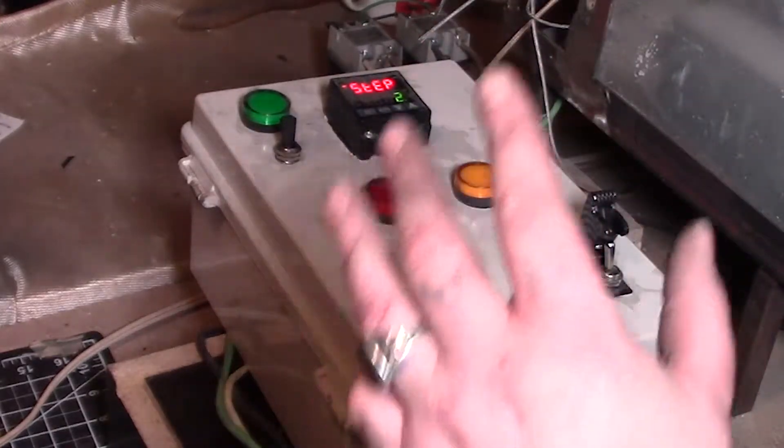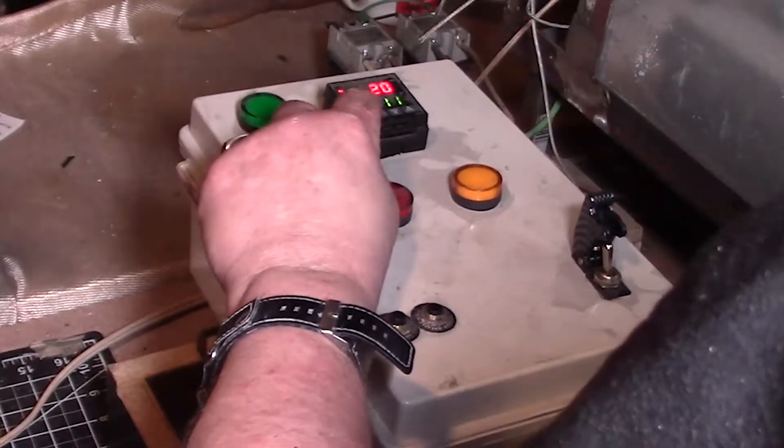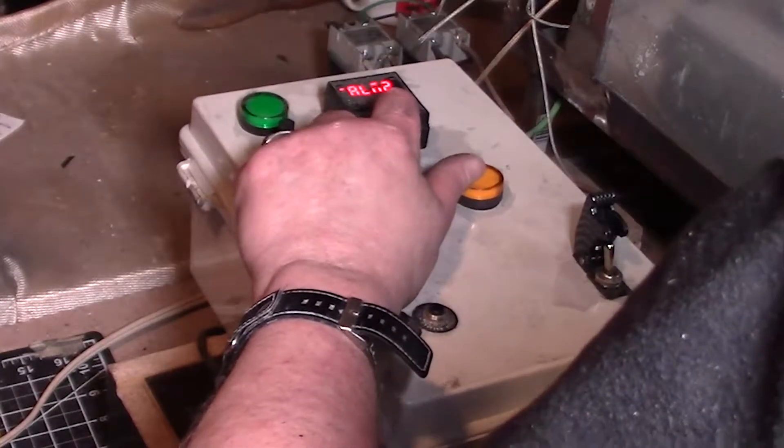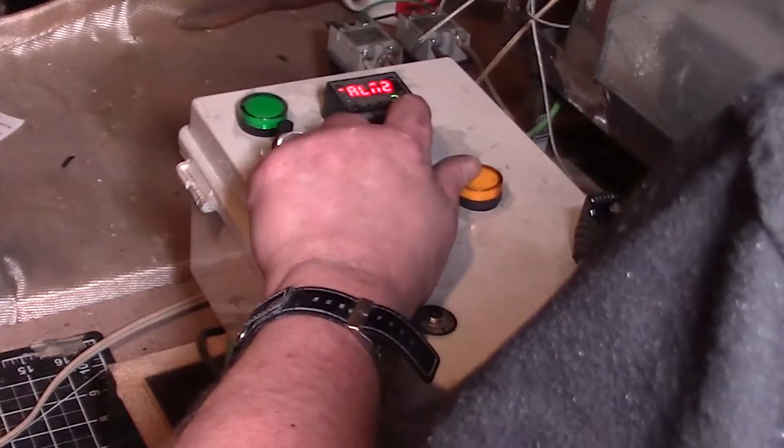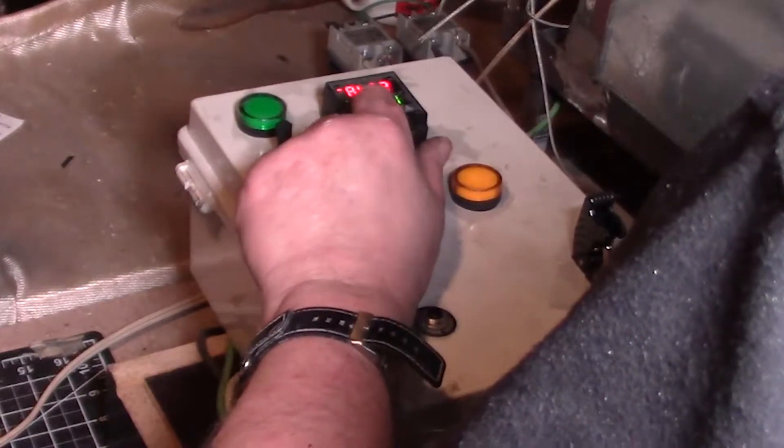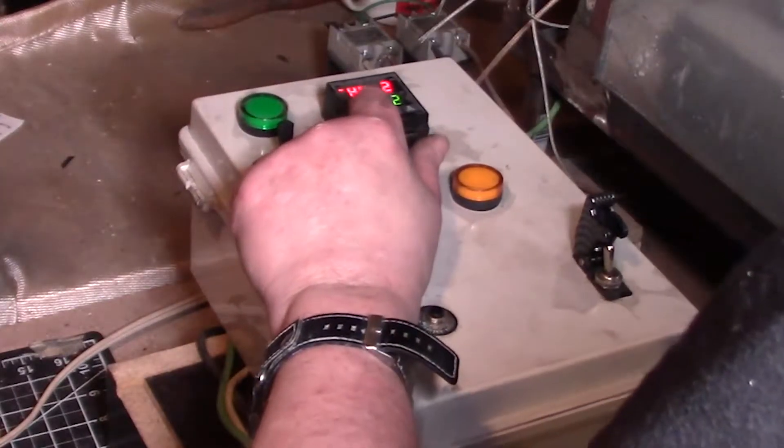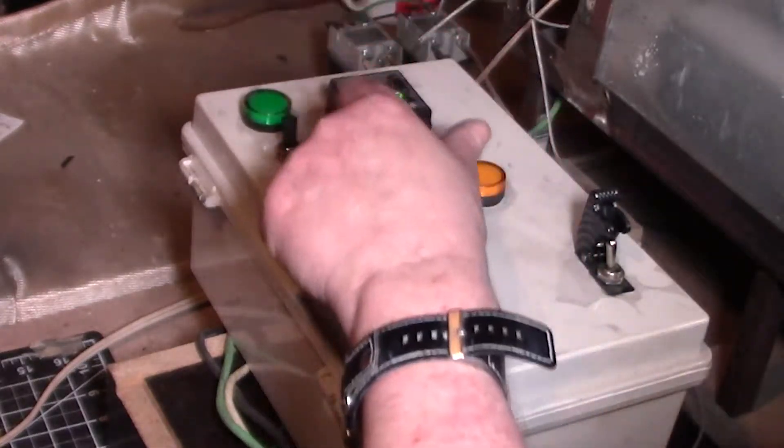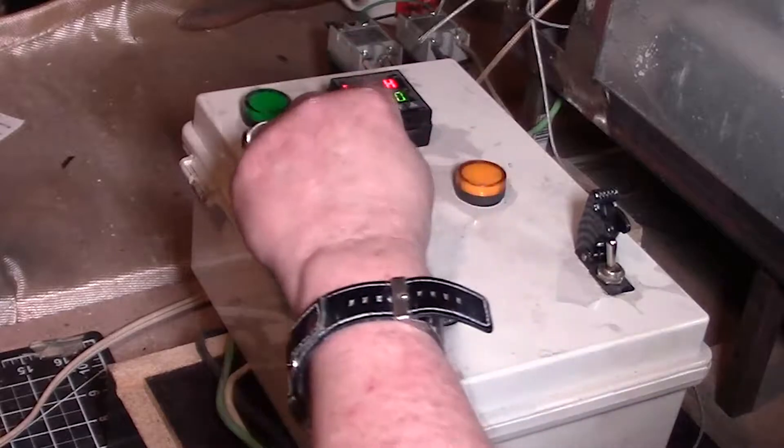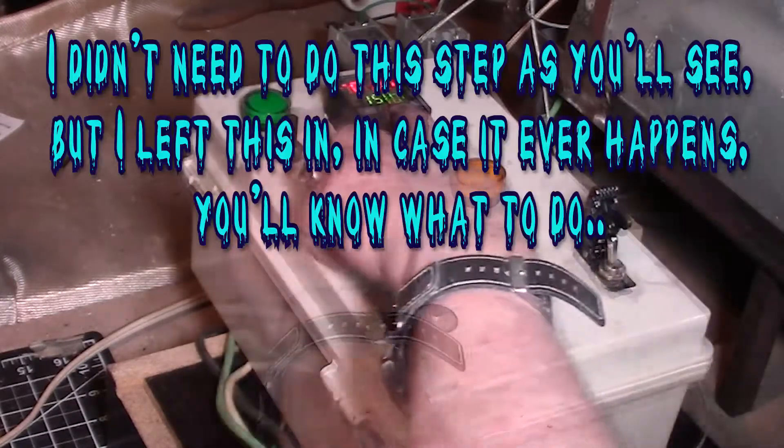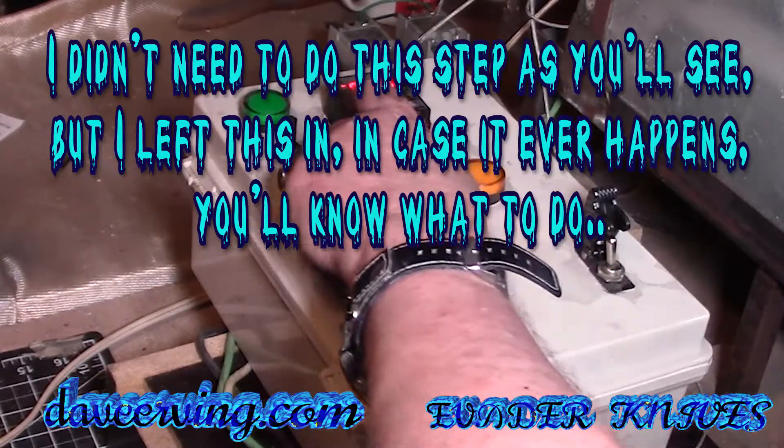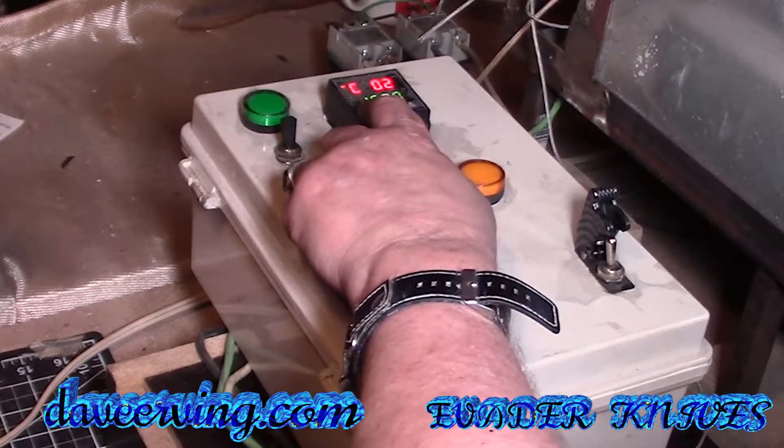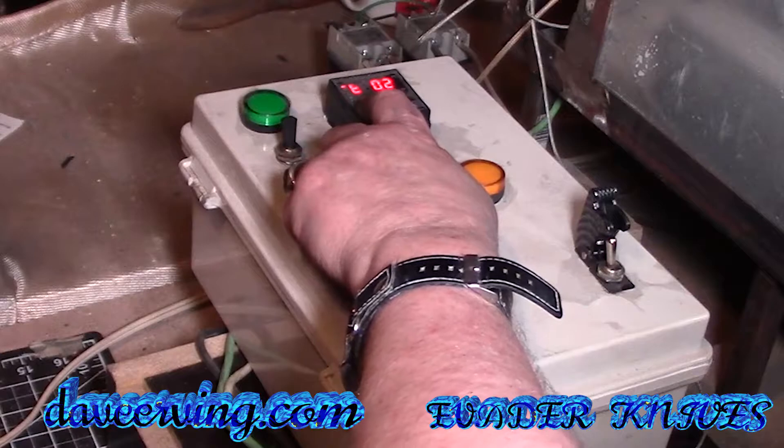Now when you auto-tune, when you put a new thermocouple, you're going to have to auto-tune it. So you hit step and you hold step alarm, then you go up to HY. It's auto-tune right there and you go down to two. You're going to have to go through your book for the rest of the stuff. 1500 is about where I do everything, so step 2 timing, step 3, we'll just keep it at 1500. Then you let it sit.